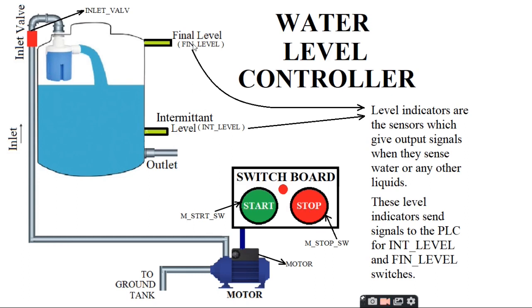There are two level indicators: an intermittent level and a final level. Once the motor is turned on, water flows from the ground tank to the upper tank and starts filling. These level indicators are sensors which give output signals when they sense water. They send signals to the PLC for the INT_level and FIN_level switches.